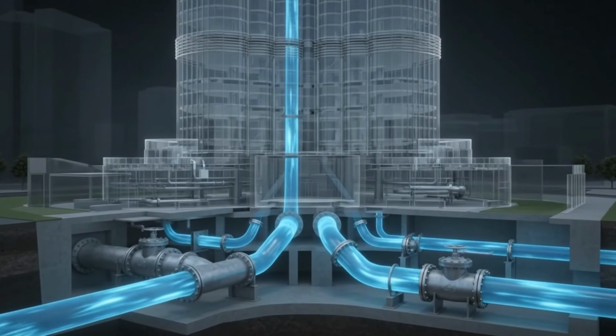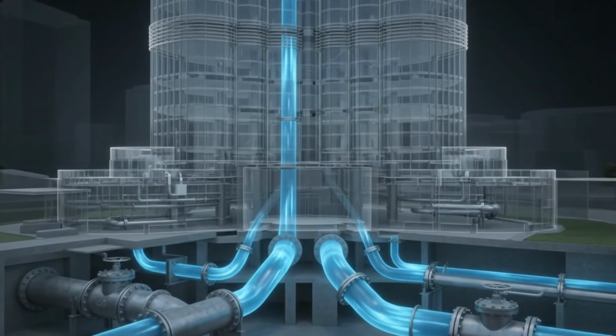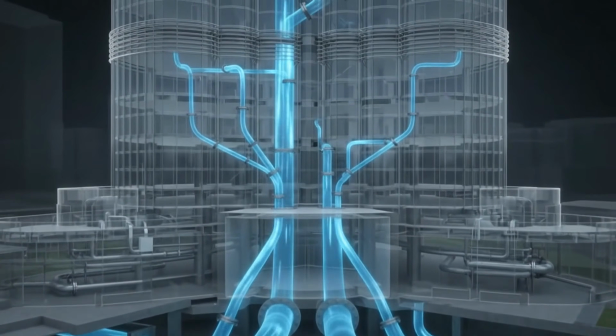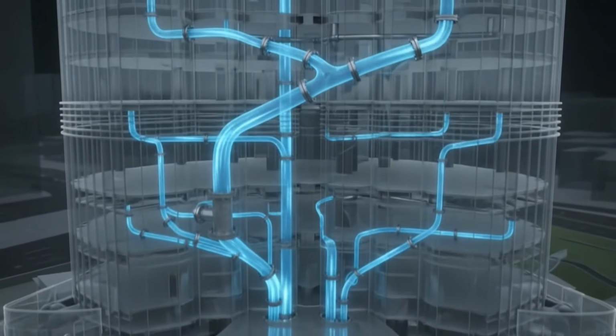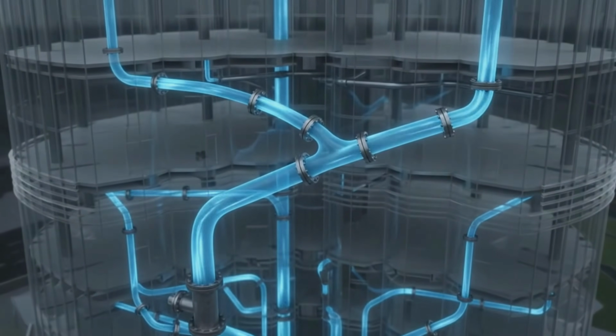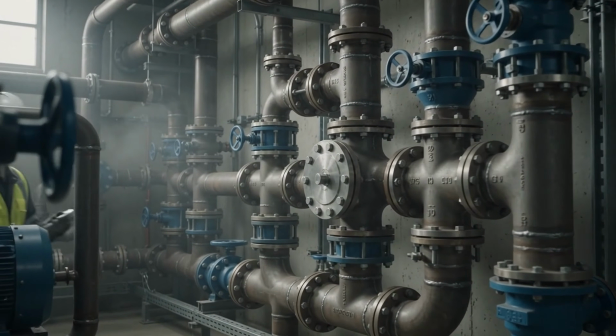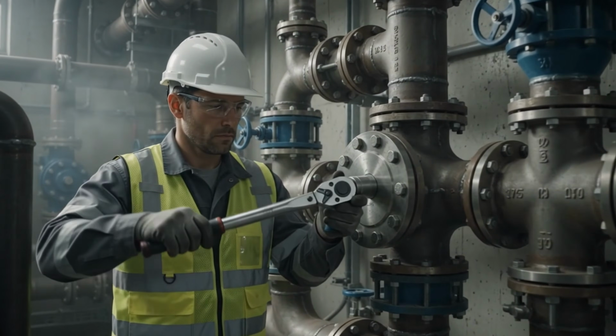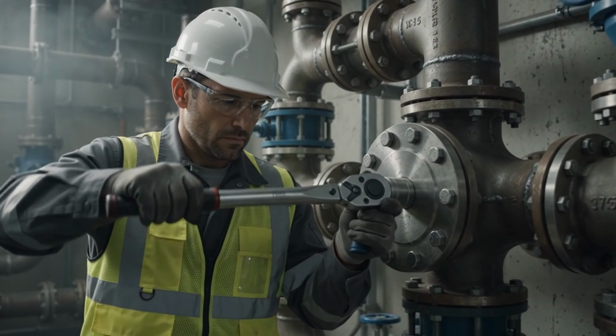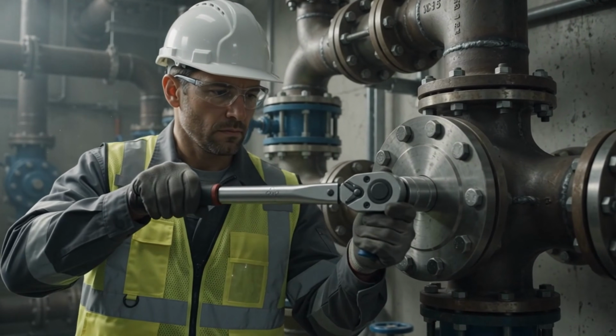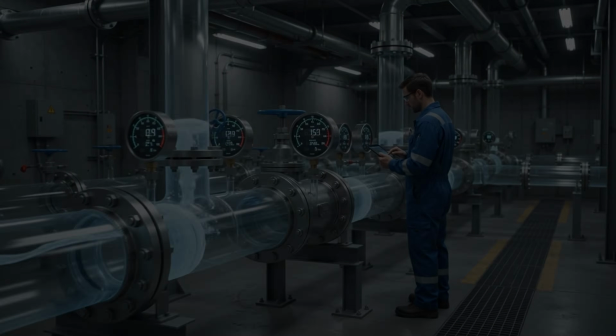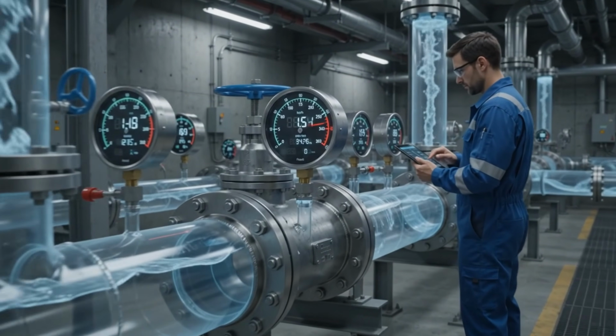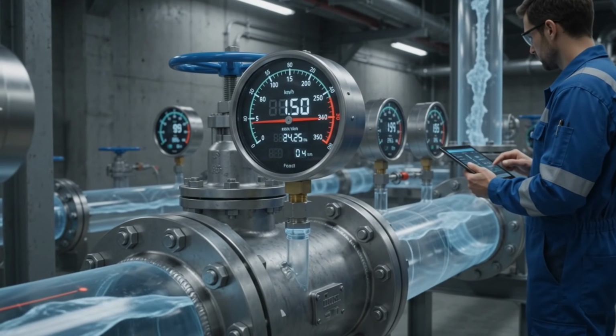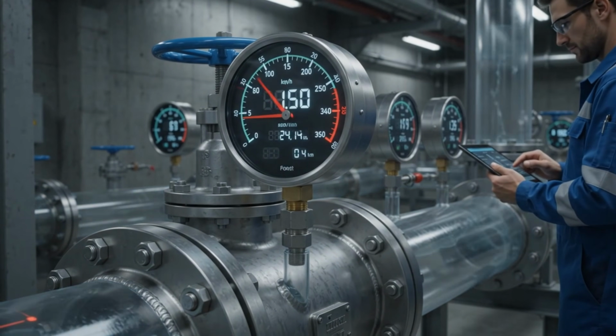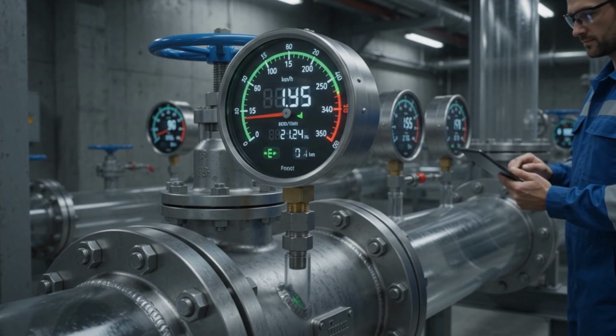Pipe diameters are carefully sized throughout the system. Large mains carry high volumes at low velocity in the basement, while smaller branch pipes at upper floors maintain pressure. Every fitting in the system is torqued to exact specification. Over-tightening can crack pipe materials, while under-tightening risks leaks under operational pressure. Before any section of pipe is commissioned, it undergoes hydrostatic pressure testing, pressurized to above operational levels and held for 24 hours to confirm zero leakage.